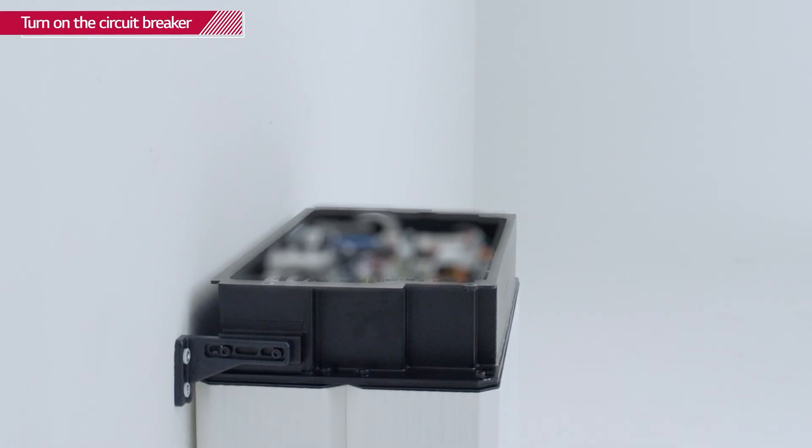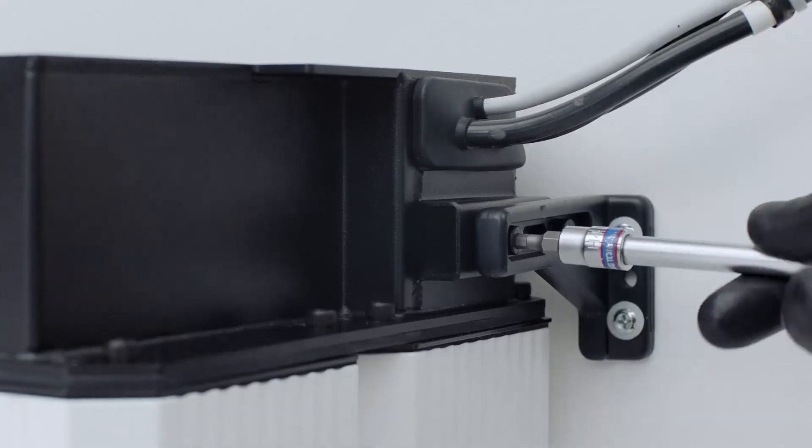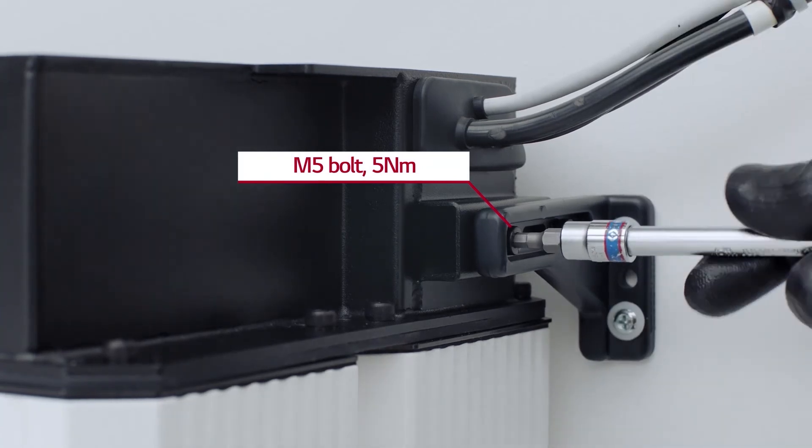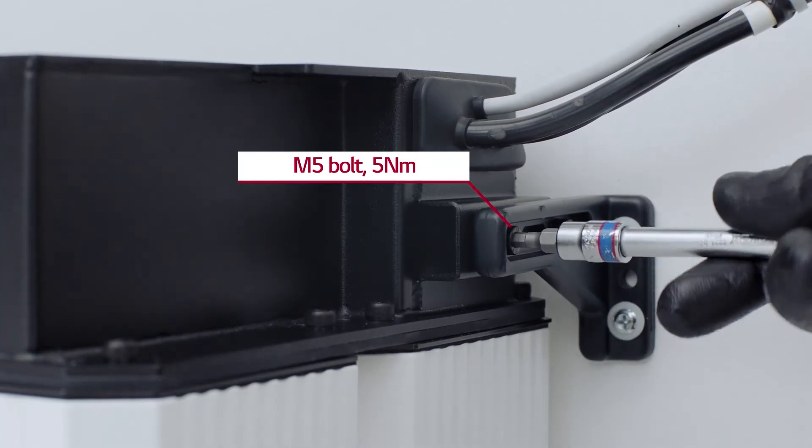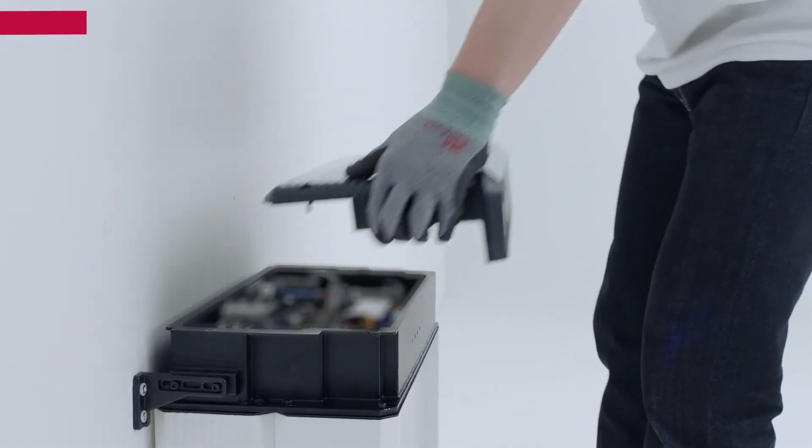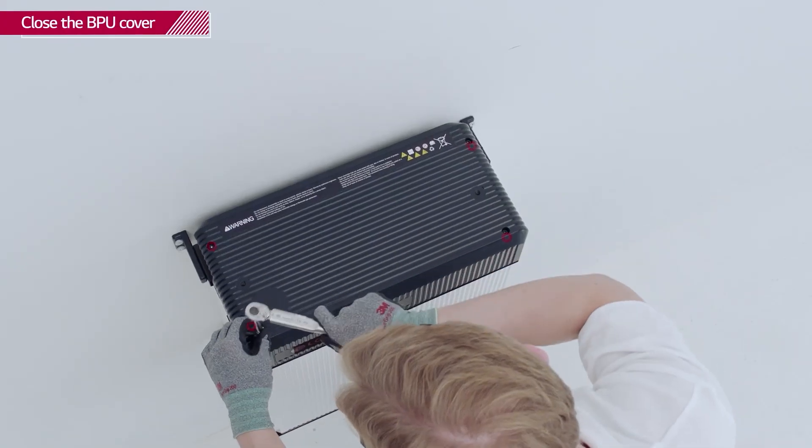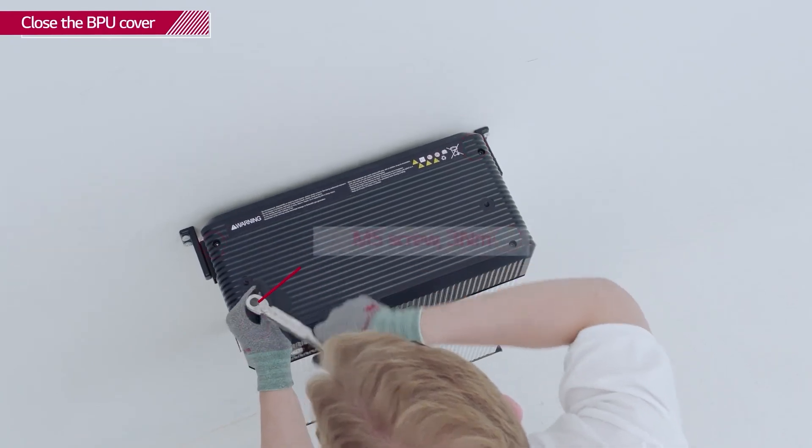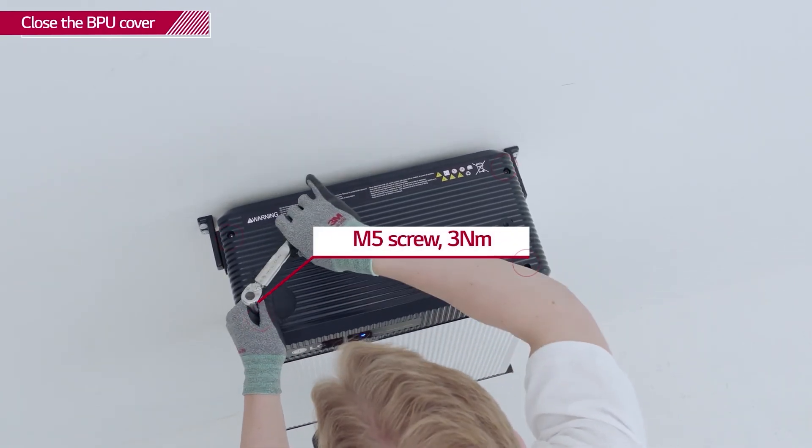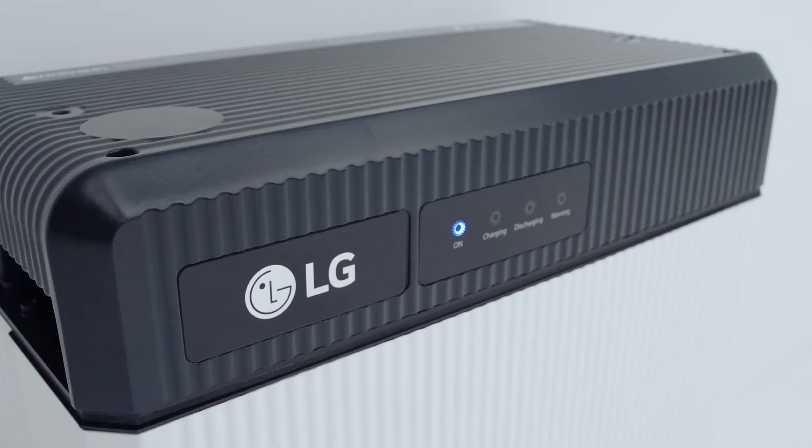Place the BPU between the mounting brackets. Fix the BPU to the mounting brackets with M5 bolts with a torque of 5 Nm. Close the BPU cover and tighten the 4 hex socket screws with a torque of 3 Nm.